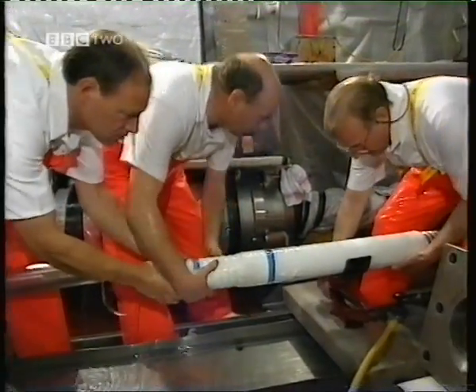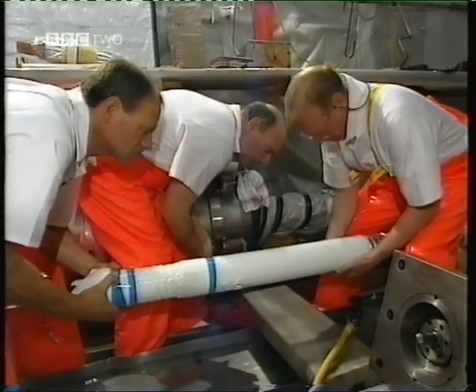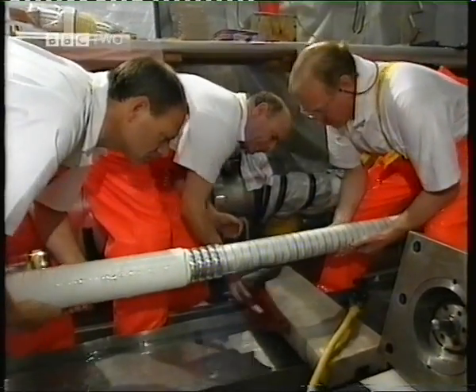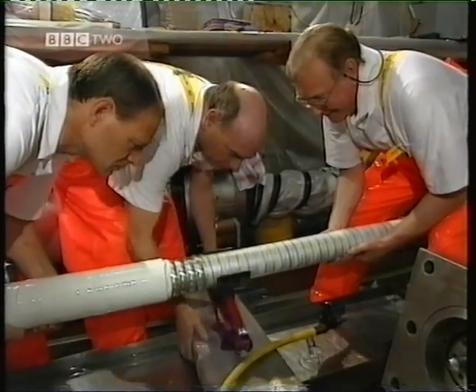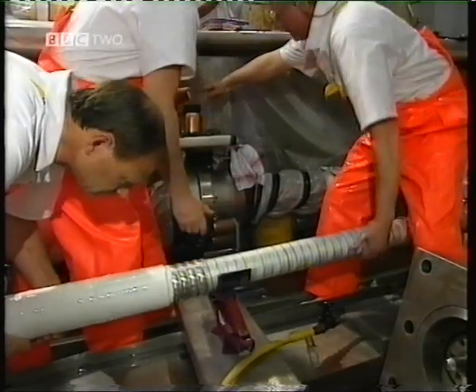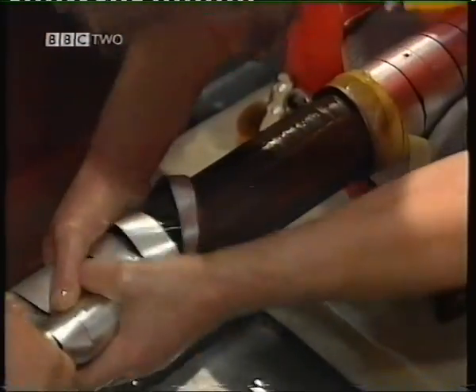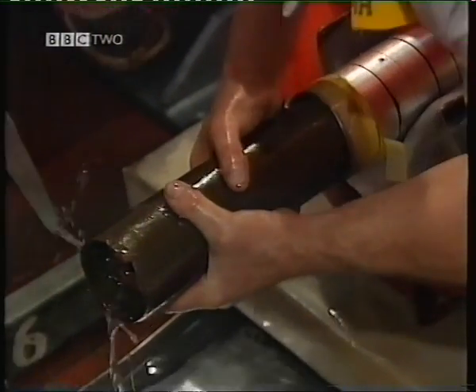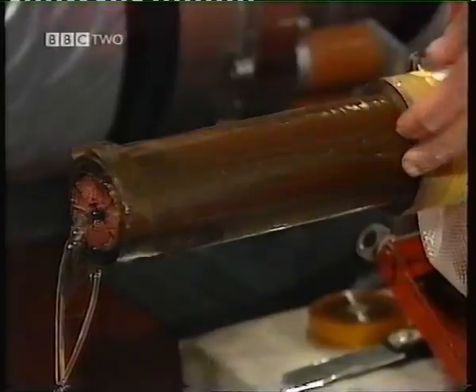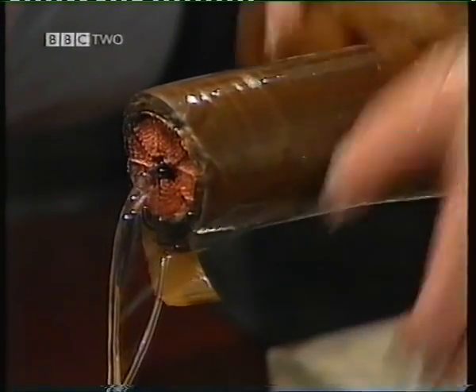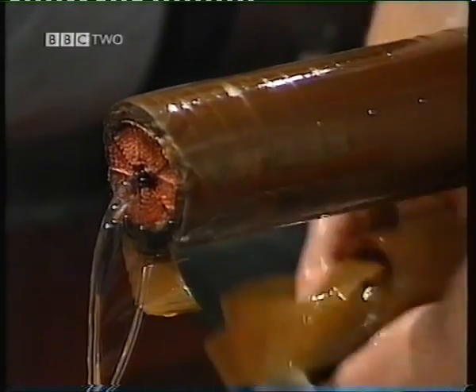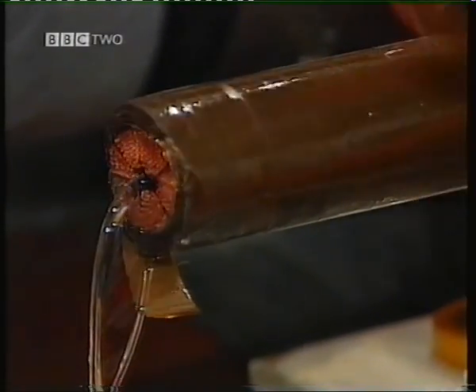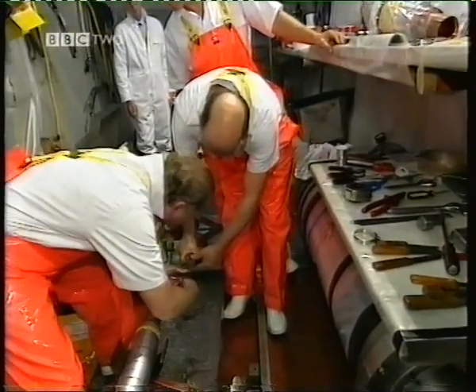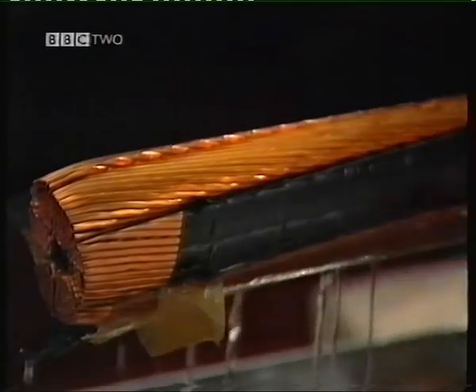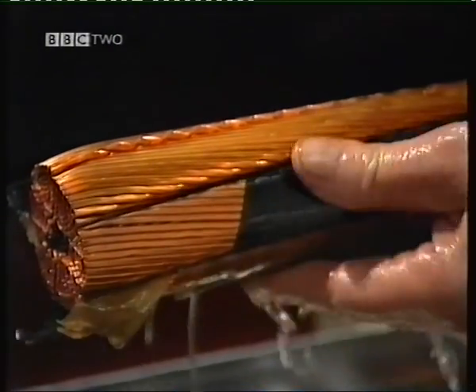Preparation for the jointing gives us the ideal opportunity to see how the cable's made up. There's an aluminium sheath around the outside to contain the internal oil pressure and for other electrical reasons. The basic principles are just as in the early days in London. The insulator is oil-impregnated paper. It's hard to do better than this combination. This cable's rated at 275 kV and incorporates a hollow core between the strands through which oil permeates to assist the cooling. There are variations on this design which can use compressed gas or hardened plastics as the insulator. As well as being the electrical insulator, the oil can also carry heat away by convection, in contrast to polymeric solids, which are inherently poor conductors of heat.